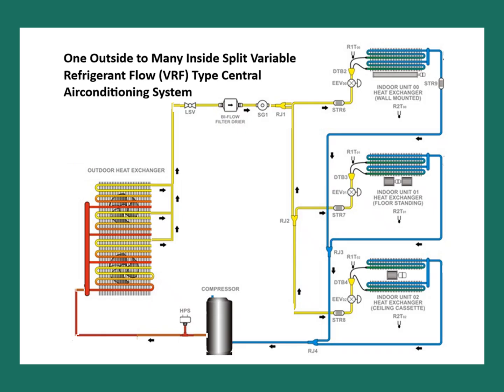Friends, the VRF system utilizes the concept of one outside to many inside split variable refrigerant flow type central air conditioning system. Now you can see clearly that this is one outside unit, that is the condensing unit, and the compressor, and the many inside units. Here I have shown only three inside units. And the expansion valve is in between.